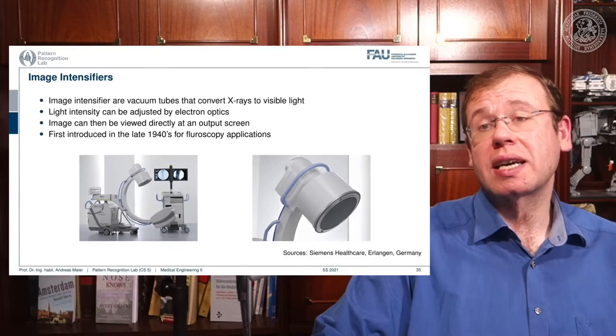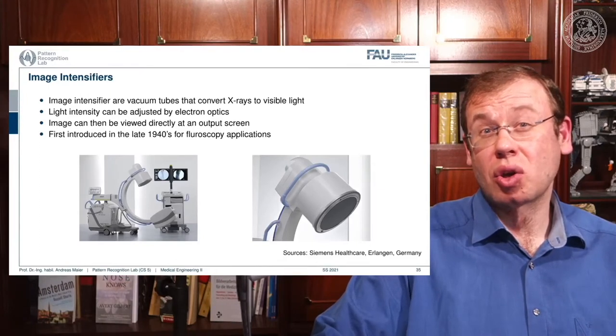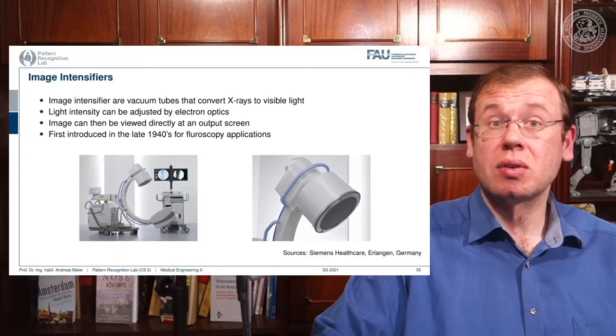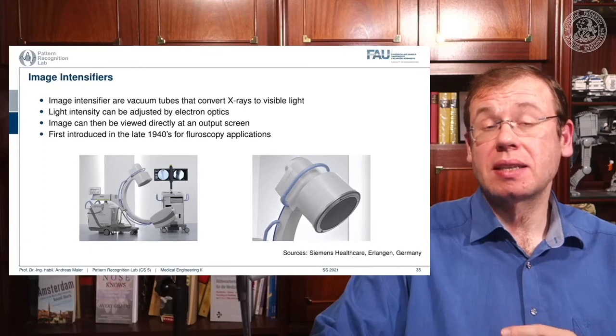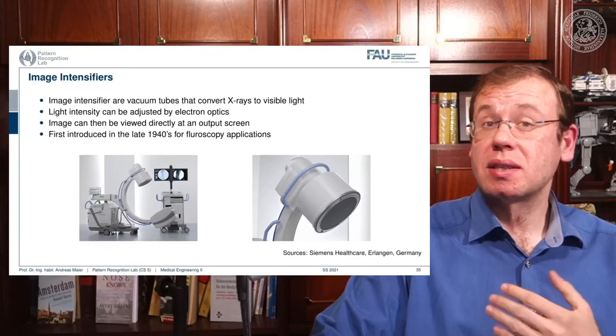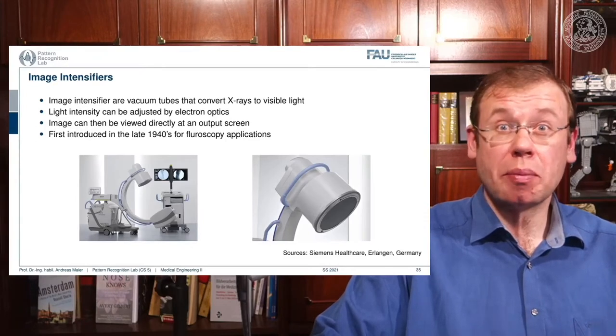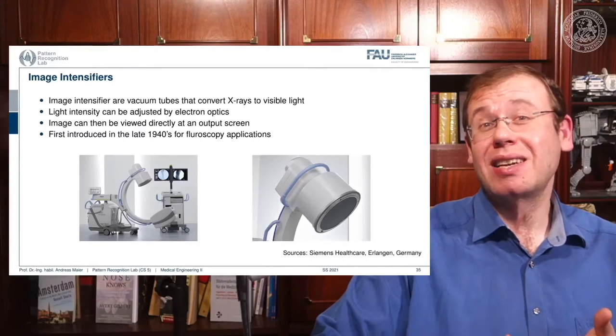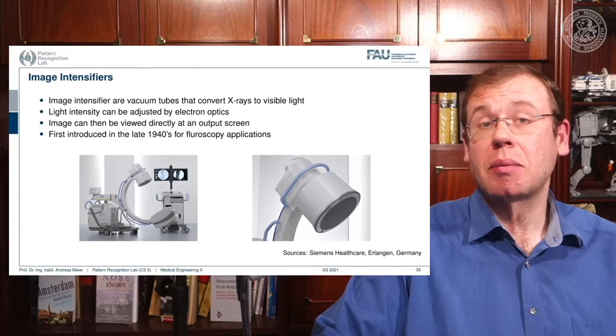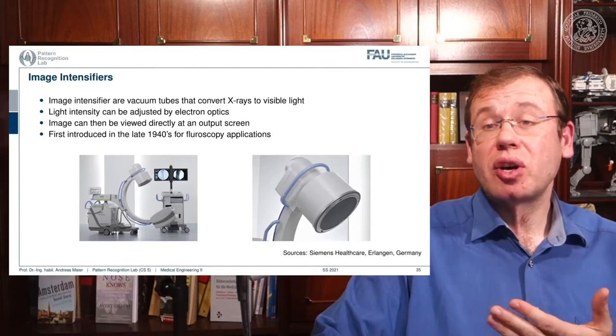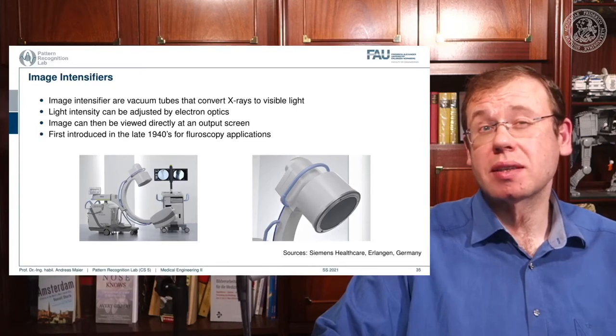We will discuss image intensifiers and flat panel detectors — these are two key technologies used to detect x-rays. Nowadays most systems use flat panel detectors, but if you see an image intensifier you should know how it works, which is why we still cover it here. We also want to discuss sources of noise in x-ray imaging. X-ray image intensifiers are essentially vacuum tubes that convert x-rays into visible light, and the nice thing is that we can adjust the magnification in these systems.